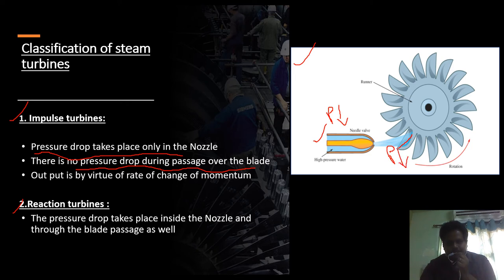In case of a reaction turbine, pressure drop takes place inside the nozzle as well as through the blade passages. This type of turbine is called a reaction turbine. To summarize: in an impulse turbine, pressure drop takes place only in the nozzle; in a reaction turbine, pressure drop takes place in the nozzle as well as through the passage of the blade.